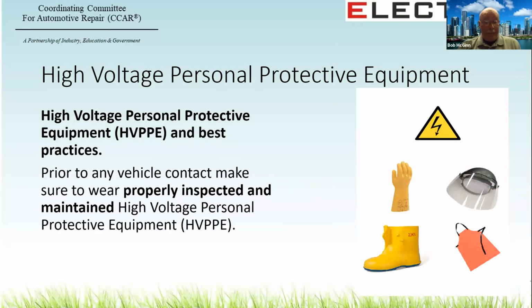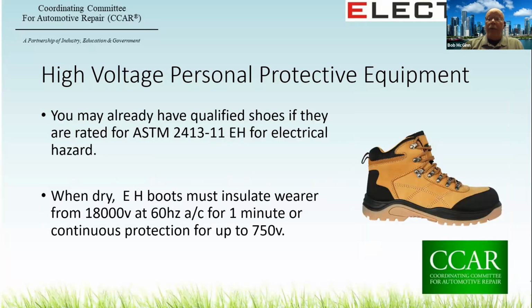So let's talk about PPE. Before you work with high voltage, you need the right high voltage personal protective equipment. And what we in automotive call high voltage, the personal protective equipment manufacturers refer to as low voltage, or in some cases, ultra low voltage. Some of you may already have qualified PPE and you may not know it. You may have already had qualified shoes if they're rated for 2313 or 241311 EH for electrical hazard. When your boots are dry, they would insulate the wearer from 18,000 volts AC 60 hertz for a minute, or a continuous protection of up to 750 volts.